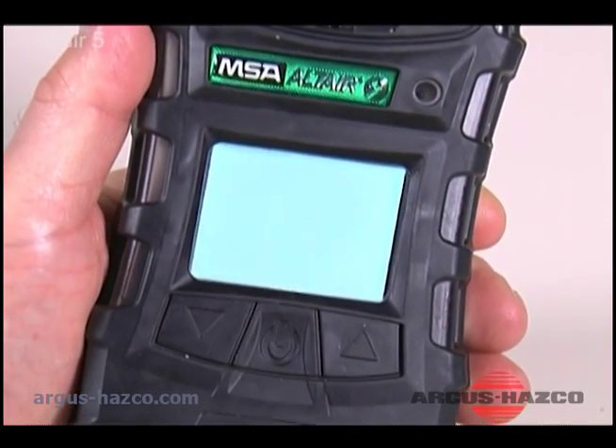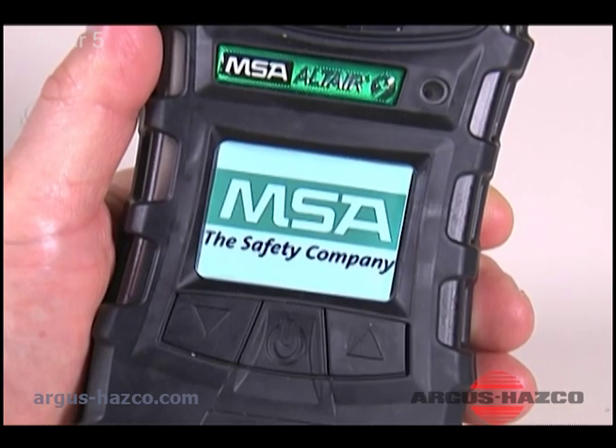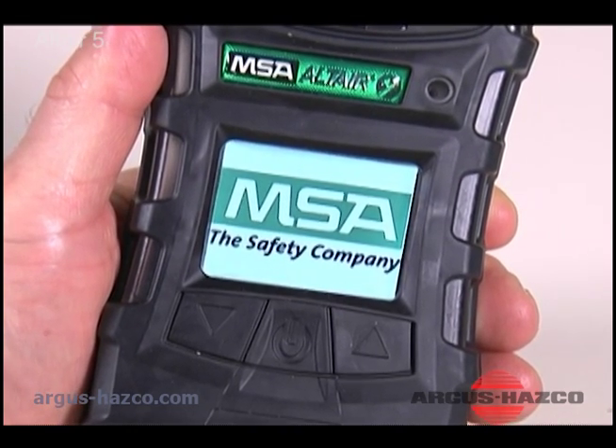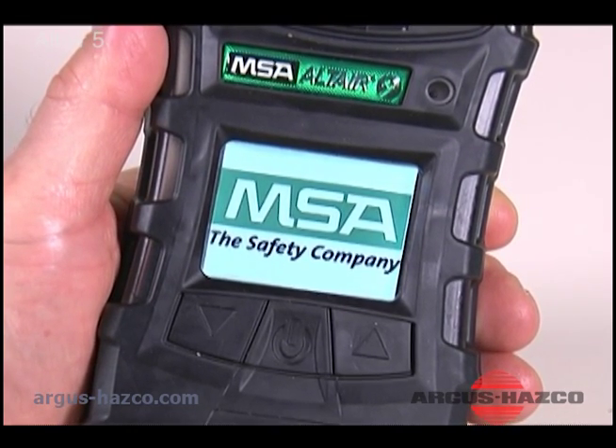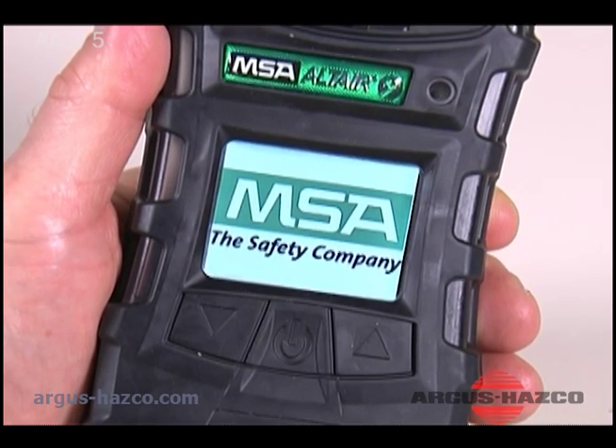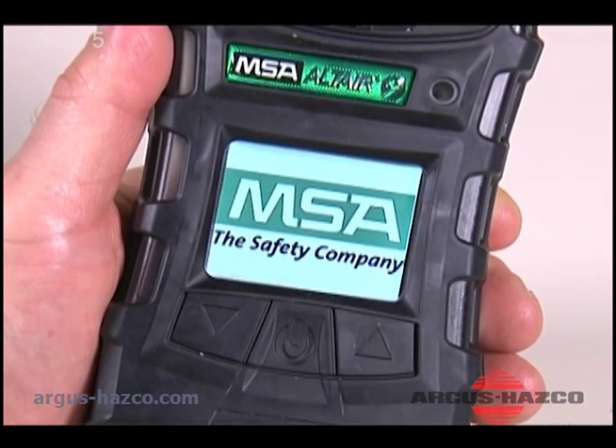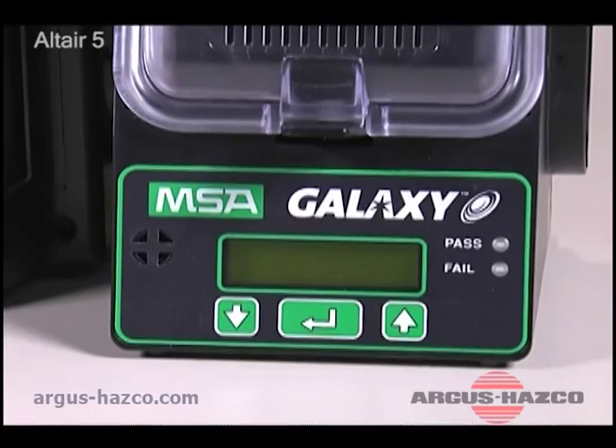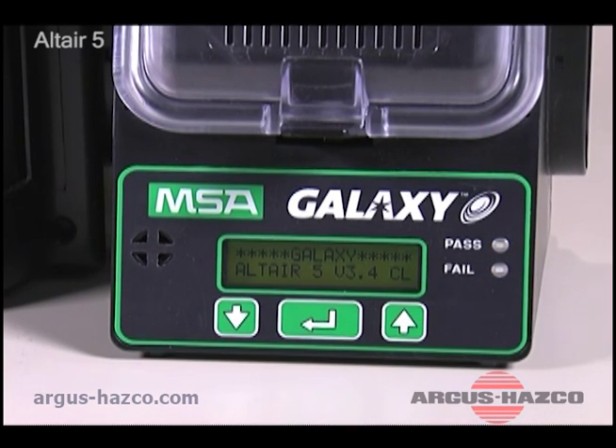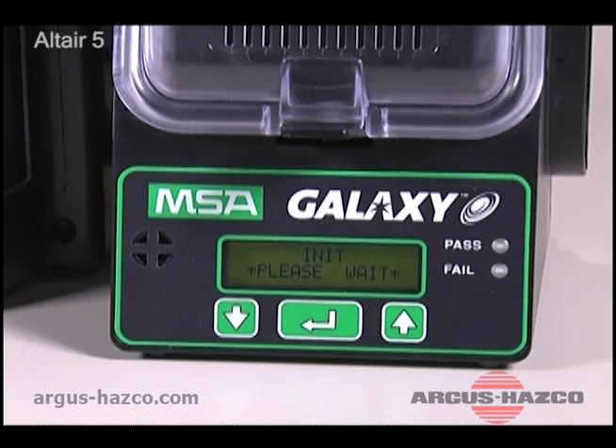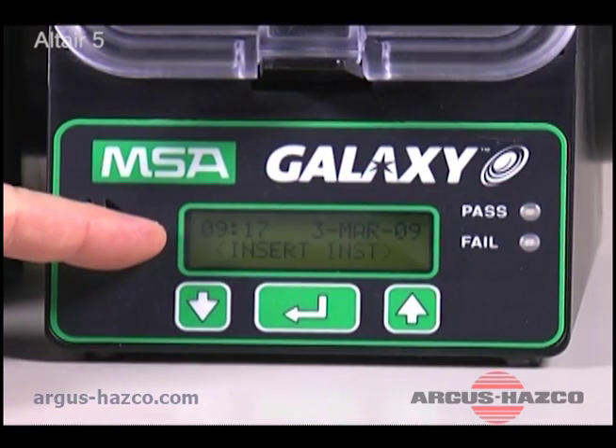Turn the instrument on and let it warm up. Instrument must fully warm up. Failing to allow unit to warm up can cause erroneous test results, which can cause inaccurate calibrations. Check the Galaxy System Test Stand LCD for the flashing Insert Instrument prompt. Do not insert the instrument until you see this prompt.